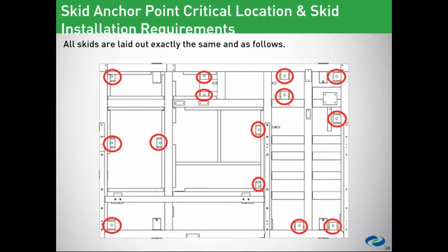So we showed the skid tie-down points. Grouting is optional due to the fact that the skid itself has virtually no vibration. And the vibration that there is, if you tie it down, has a possibility of being amplified. You'd have to have a perfectly smooth setup, so shimming would probably be required to take that out. I can't think of anything else to say.